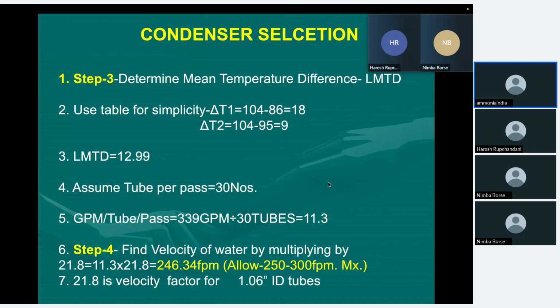As we discussed, it is the mean temperature. The delta T1 is 104 minus 86 is 18. Delta T2 is 104 minus 95 is 9. So LMTD, log mean temperature difference, is 12.99. Now we have to assume certain tubes per pass to start with. So assume 30 tubes per pass. So GPM per tube per pass will be 11.3 GPM.